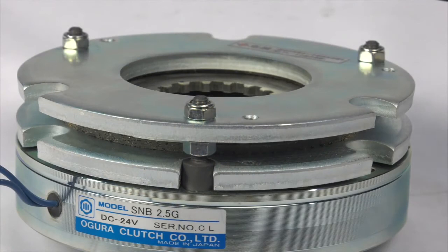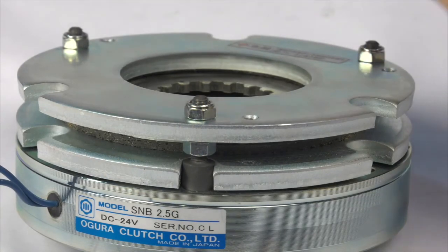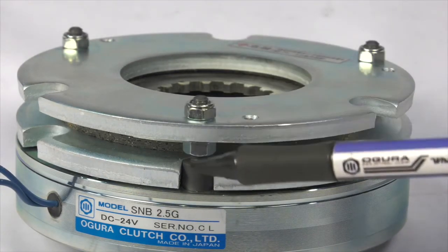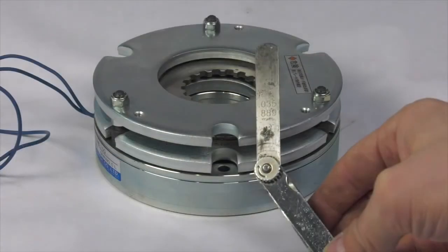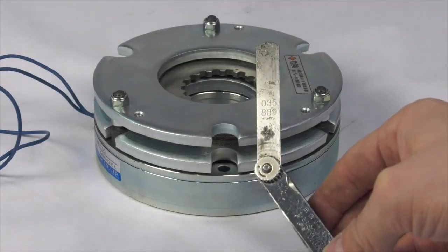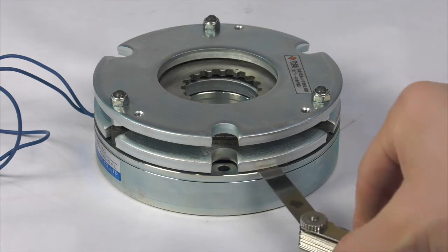To reset the gap, loosen the inner adjustment nuts under the brake cover plate. Tighten the outer nuts until the proper air gap is set, then tighten the inner nuts against the cover plate to set the gap.